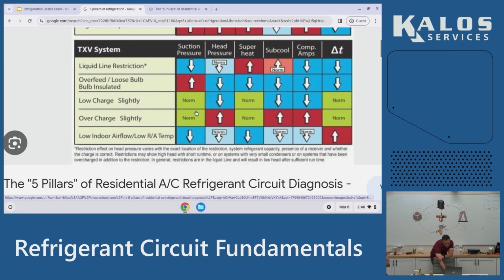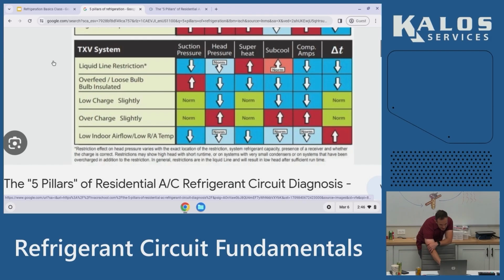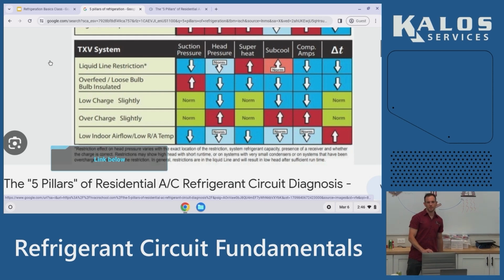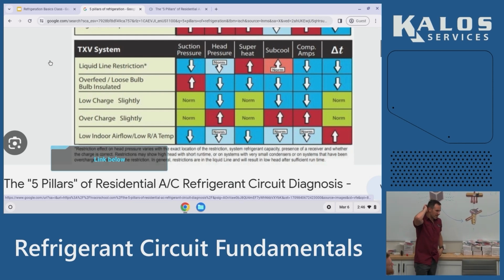And this is what Bert's talking about, is a lot of these look similar, but there's key differences. So the difference between a low charge and a liquid line restriction, right? The difference between low airflow and a low charge. You're gonna see some key indicators that tell you what the problem is. So this is a good reference chart if you look that up, or you look for that in HVAC School.